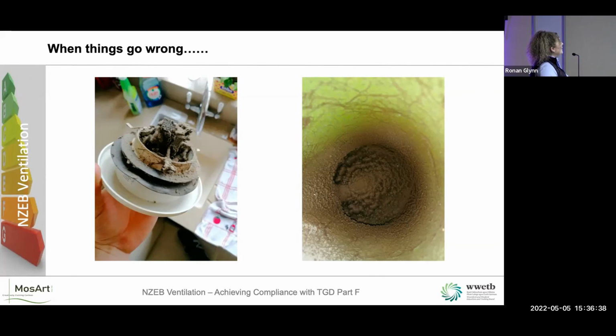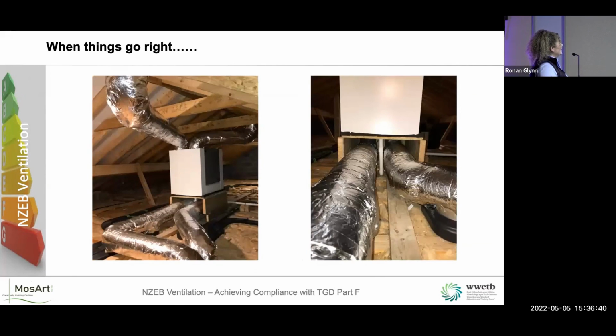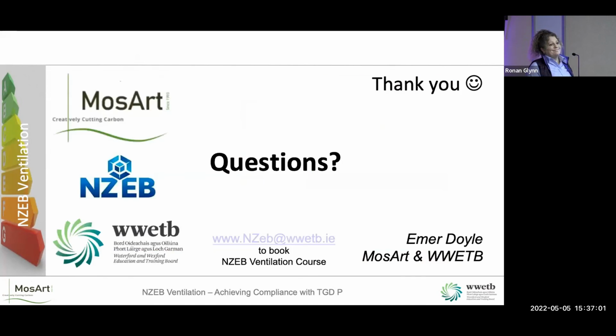So then, even though this is up in the attic, this is an example of how you can do it right. So there's a good depth of insulation on that. The unit's up on a stable base. These are kept far enough away, so we have our minimum of our 2 meter distance, and we're going from A to B in the shortest runs we can. We're going to have bends on them, but just minimize them and keep the shortest run of ductwork as possible. So that's it. Any questions?